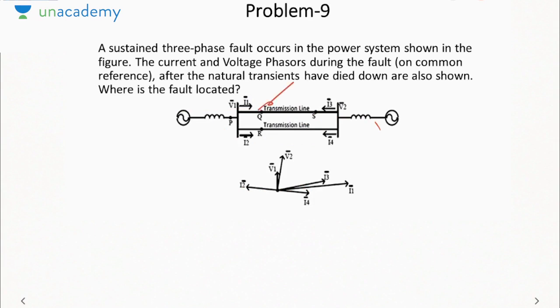If fault occurs at Q, then I1 will go into the fault, I3 will go into the fault, I4 will go into the fault like this. So I2 direction is reversed. So it satisfies all the criteria that I2 direction is reversed and the entire current goes into the fault. And the other thing that you can observe is I1 has the highest magnitude. That is, fault must be located nearest to I1.